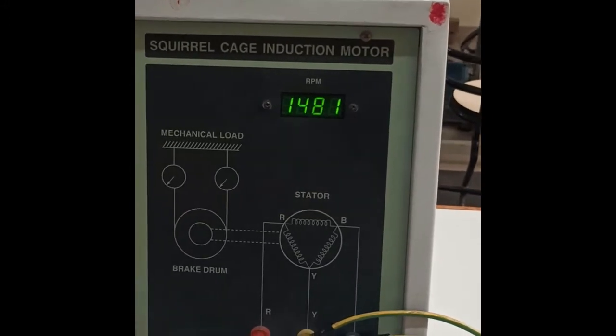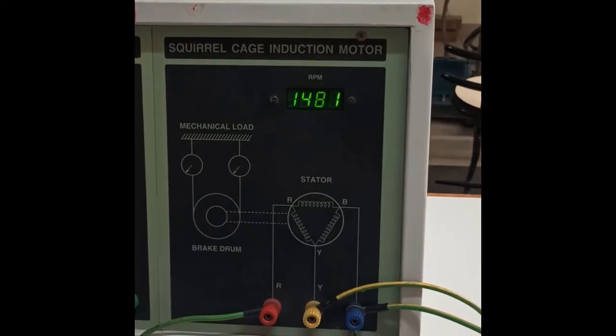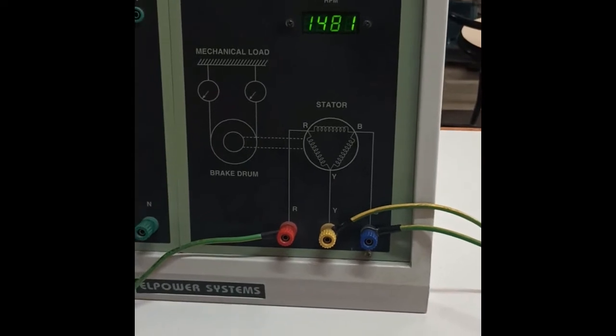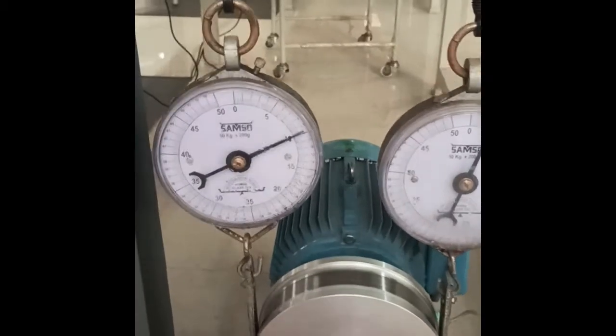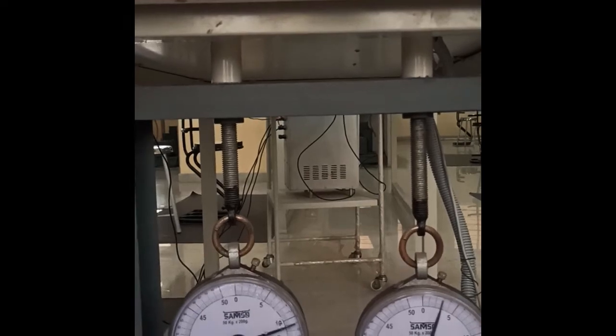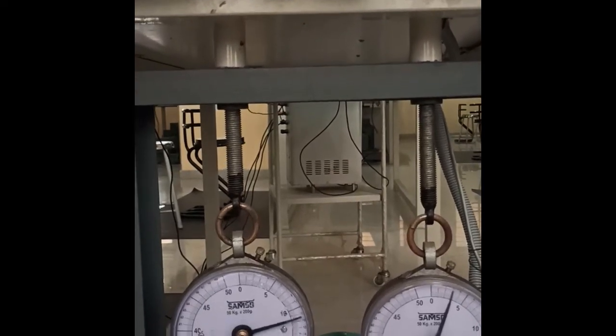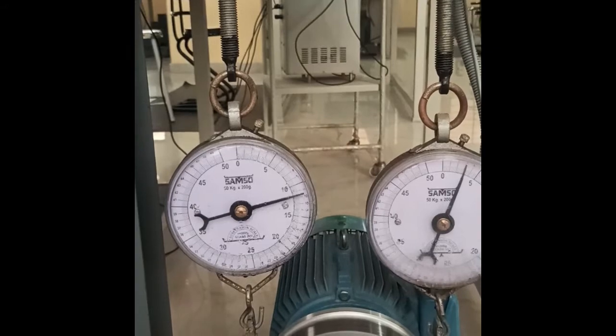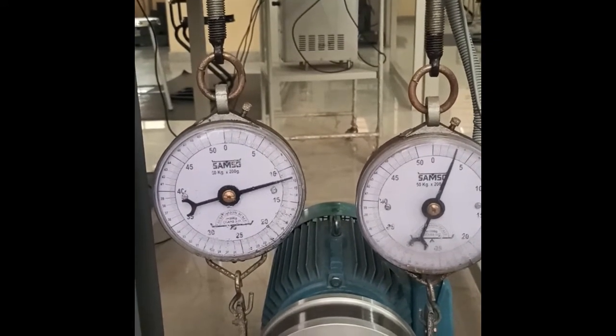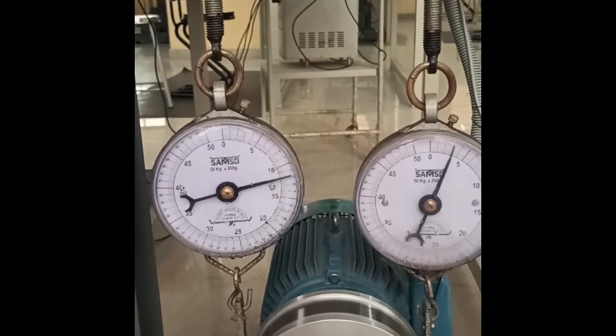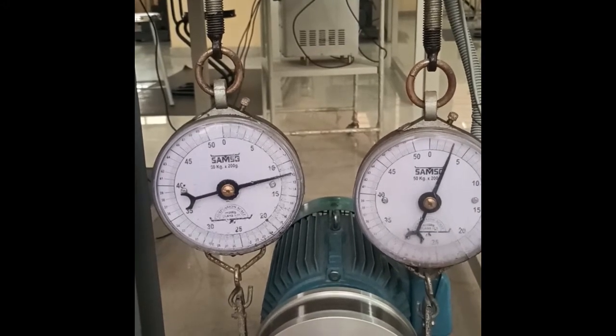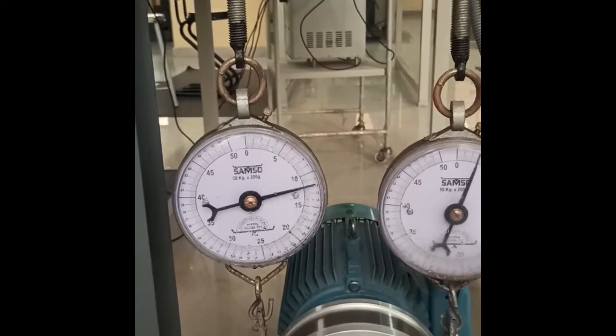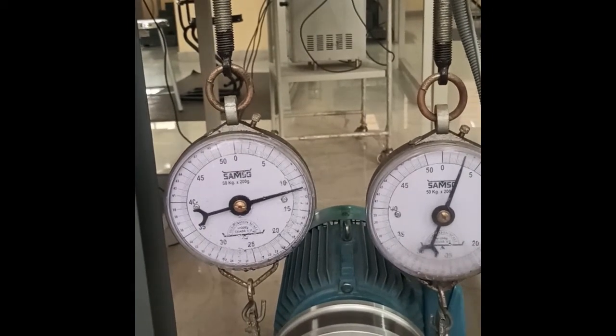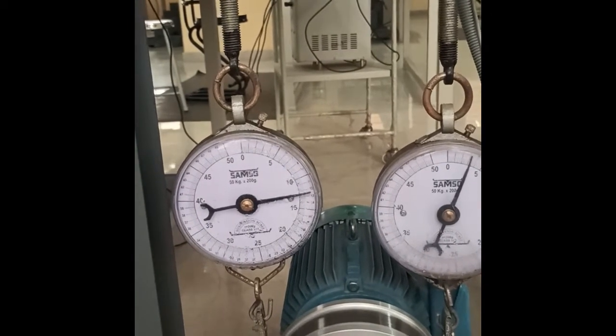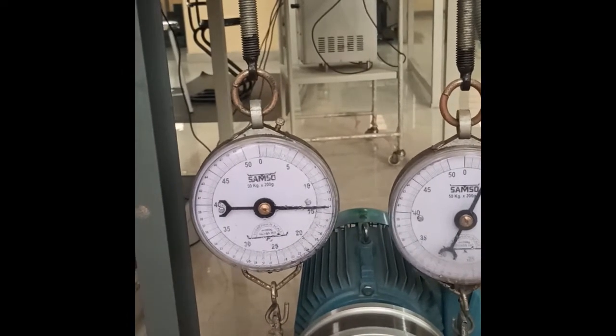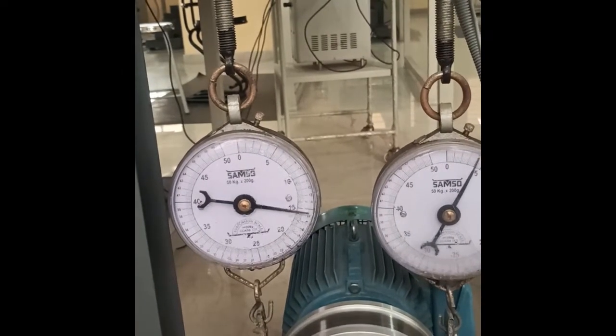Along with the voltmeter, ammeter and wattmeter readings, we have to note down the speed as well as the load under each step. So we have to go on applying the load up to the rated current of the motor, and we can increment the current by 0.5 amperes or 1 ampere and take down the readings up to the rated current. Now the rated current of this machine is given as 7.5. So go on incrementing by 1 ampere. After 4 we will note down for 5. After 5 we will note down for 6. And after 6 we will note down for 7. And the last.